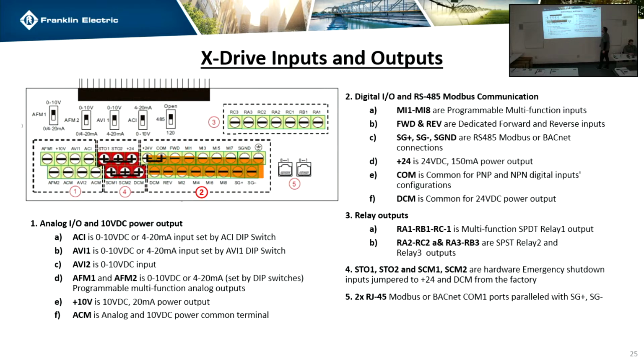For the digital inputs, it's all MI1 through MI8. On our old drives, it was M1 through M8, so they just have the I in there. Forward and reverse are dedicated inputs that are pre-programmed. Reverse is locked out. You'll have to go in and tell it not to be locked out, but it's just an input for the control. For the communications, it's all SG plus, SG minus, and ground.